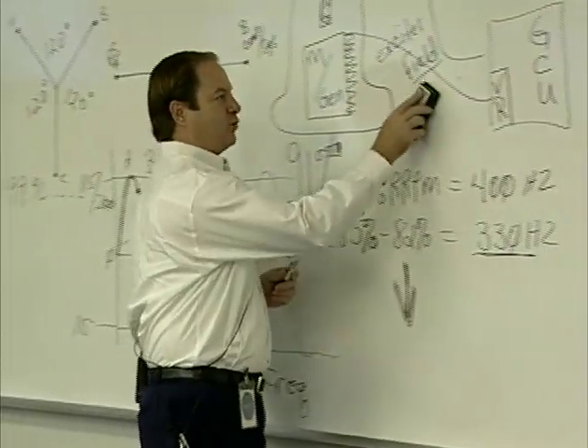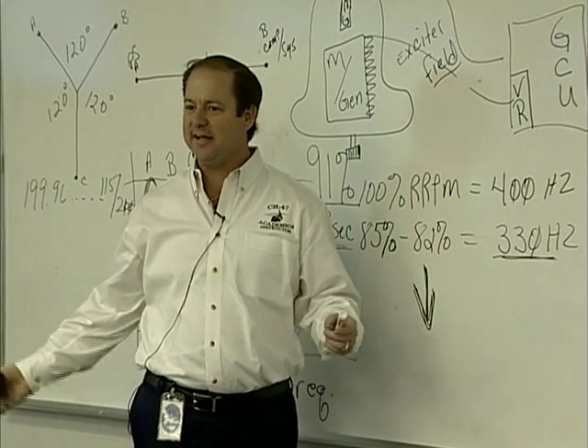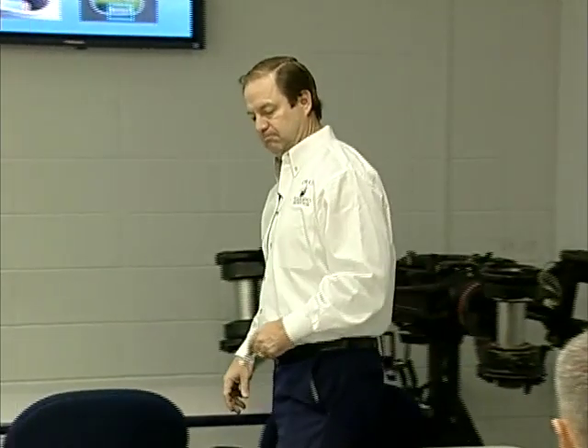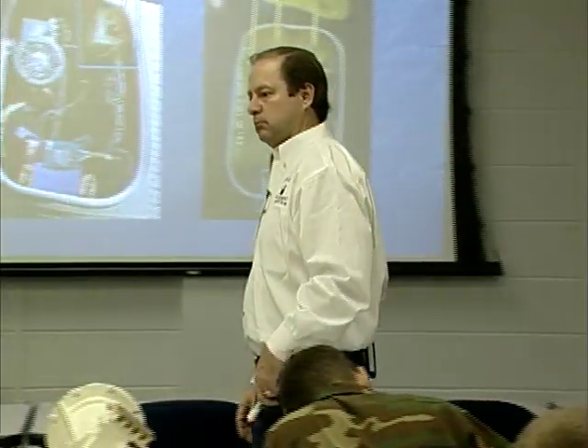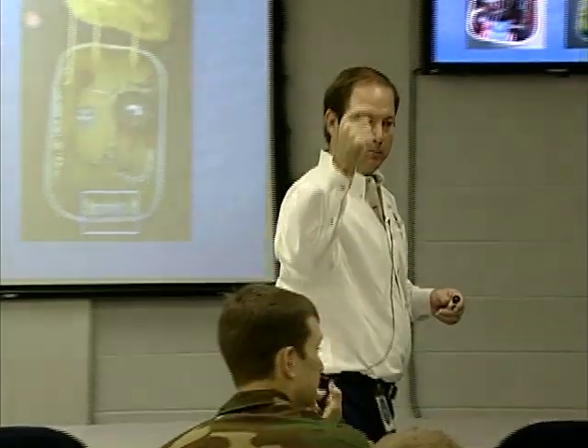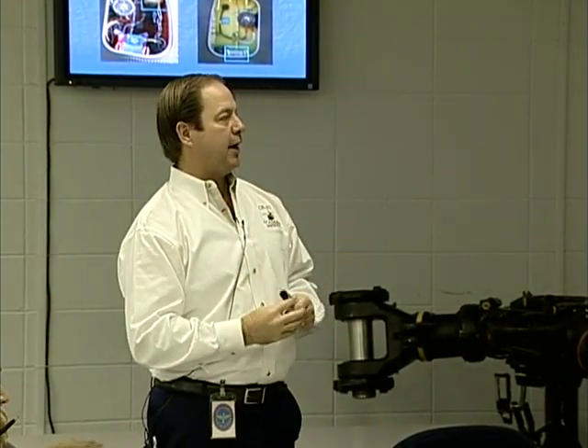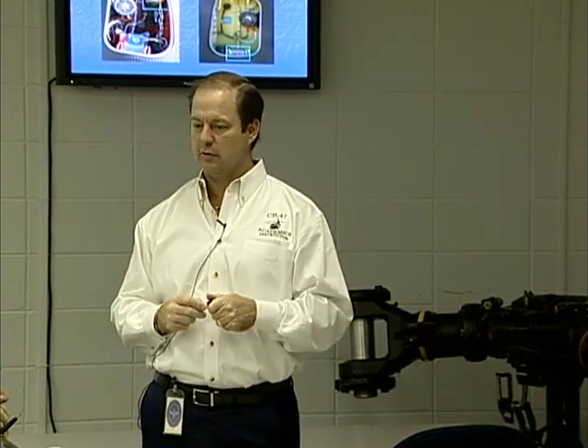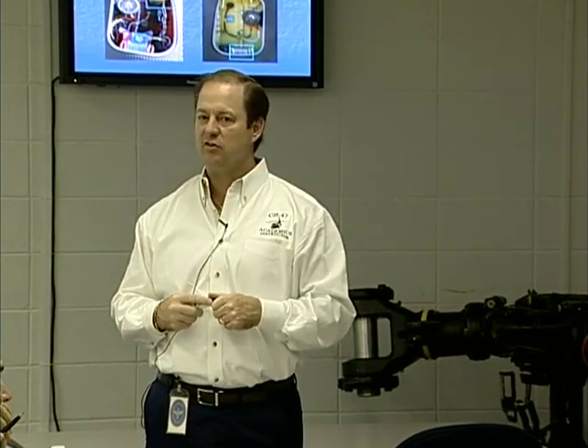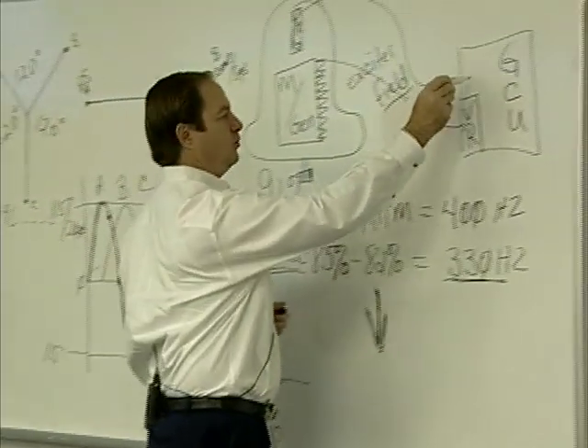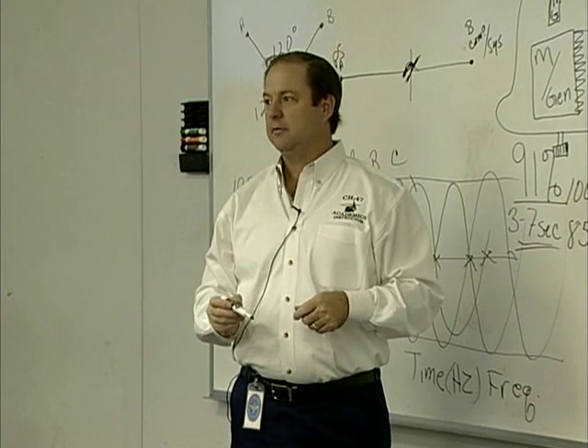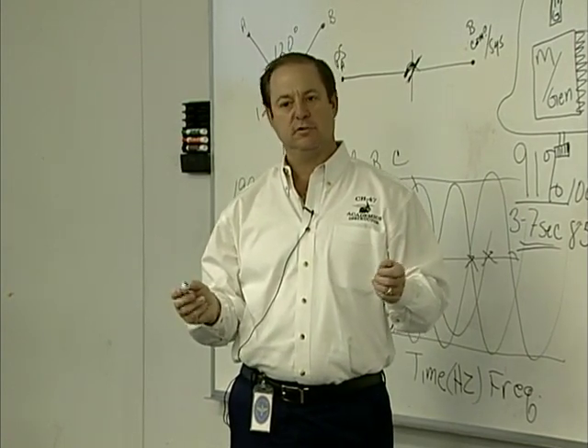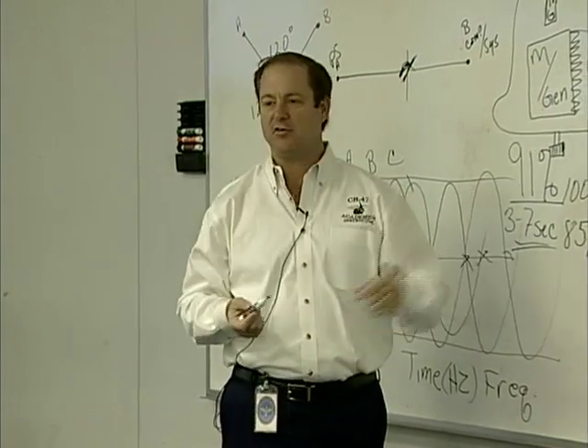The GCU is simply going to kill the exciter field. In killing the exciter field, it has now turned off the generator. But what do we know about electricity? It surges, it spikes, it's very flaky. So it could have been a momentary thing. What's required now is to find out if the situation still exists. Reset the generator, which is going to in turn reset the GCU, saying check it again. If the fault is still there, then it's going to give you a generator off caution capsule again, and it's going to kill the exciter field again.